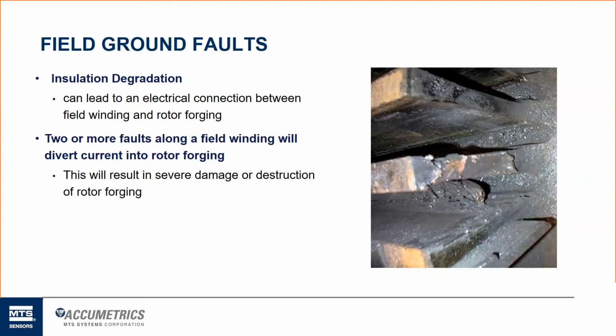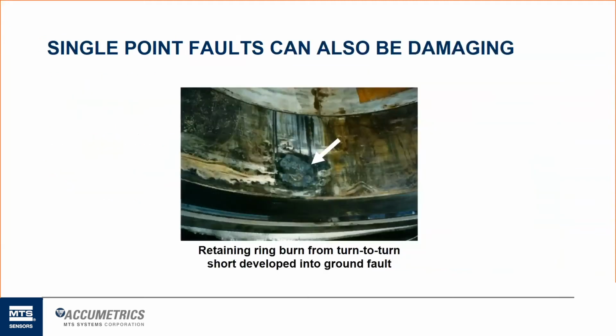It's not always true that 2 points of a ground fault are what customers are most concerned with. You can have a single point failure. And in the next slide, that shows an example. This is the retaining ring that covers those field windings that come out of each side of the rotor, where you saw them all stacked up in the previous slide. And this was from a single turn-to-turn short that developed in that and caused burning into the retaining ring that needed to be repaired.